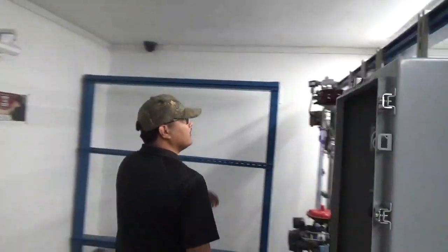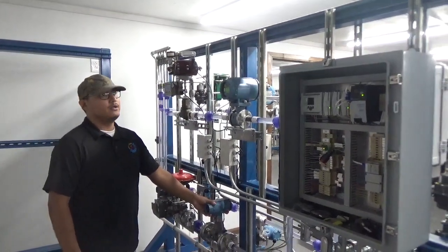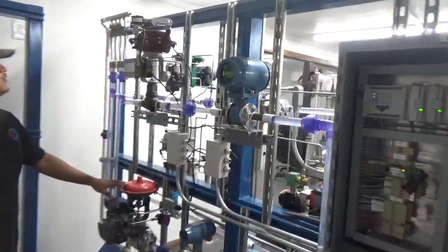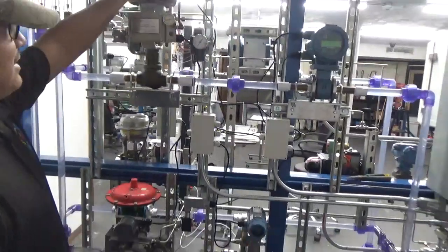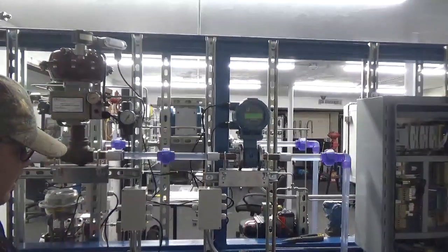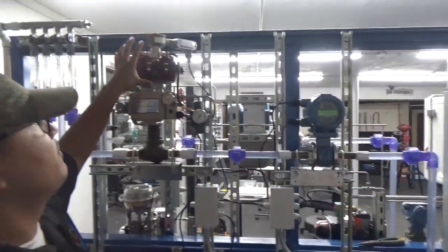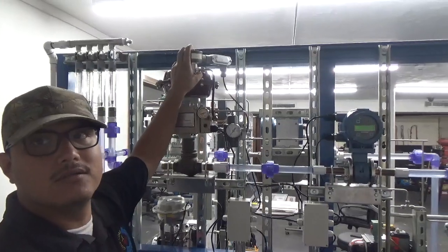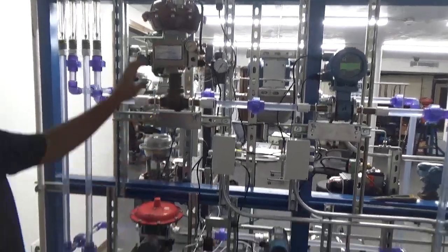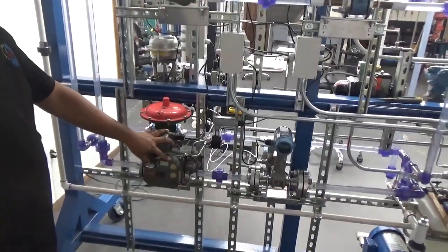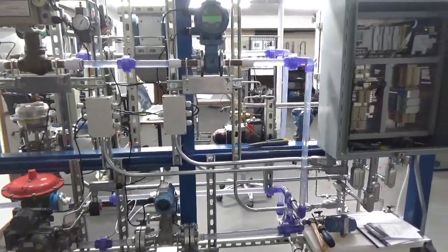On this side, we have the magnetic flow transmitter, and then the actual vortex flow transmitter with their own individual control valves. Some valves are fail open, some valves are fail closed. They have an SIS on it where these have the solenoids, 3-way solenoid valves, where if an upset does occur, then it doesn't matter if the system has air, these valves are going to cause this actual system to fail regardless of the situation. So once again, these right here are their own individual positioners that we teach our students pretty much how to mount them, how to configure them, and how to actually troubleshoot them in the real world scenario.